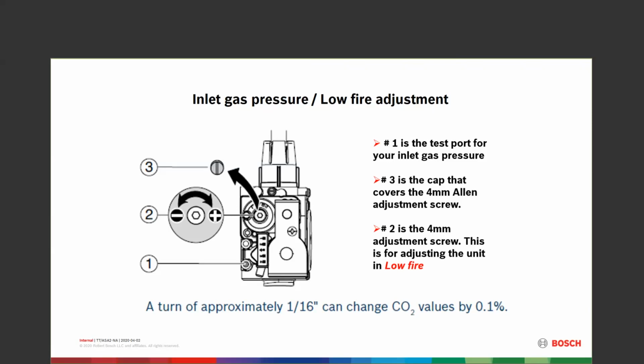They do vary a little bit, so it's not carved in stone. If you guys are having a hard time starting this, and it's something you might want to write down, if you change over to LP gas without an orifice, for instance, and the boiler won't start, on this gas valve adjustment, go all the way clockwise, all the way positive, then back out 3 full turns. And then on the gas throttle up top, go all the way clockwise to closed, back out 1 full turn, and that boiler will start almost 100% of the time.